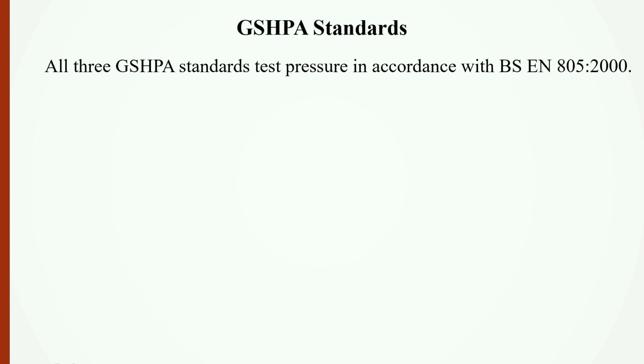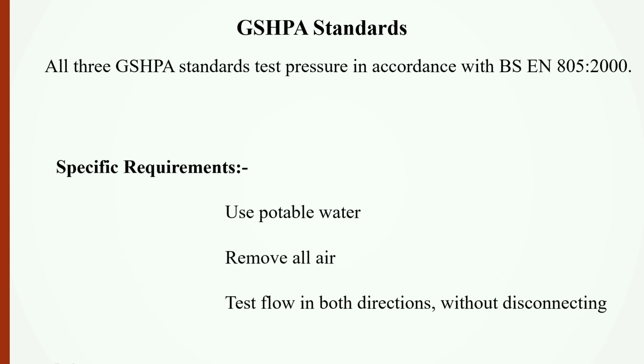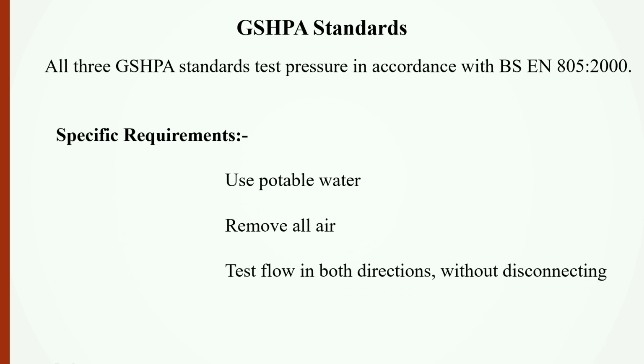So the GSHPA standards all work in accordance with BS-EN 805. They also have specific requirements in the GSHPA standard. The first is that you use drinking water. The second is that you remove all the air, because air will affect the results. And also you test the flow in that loop in two directions without disconnecting the pipework.